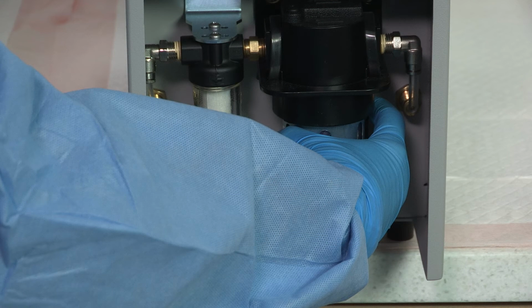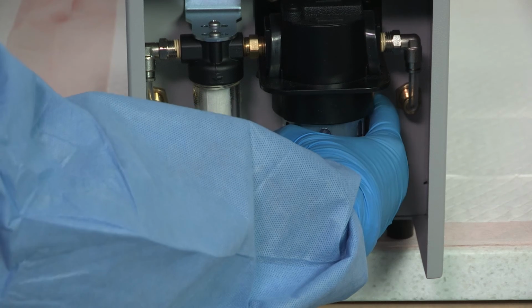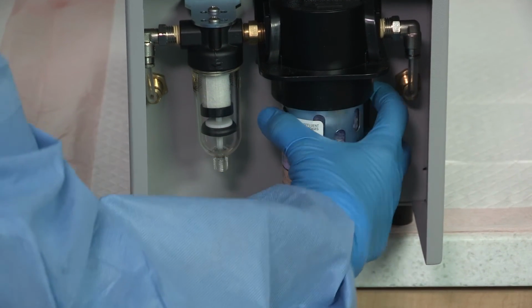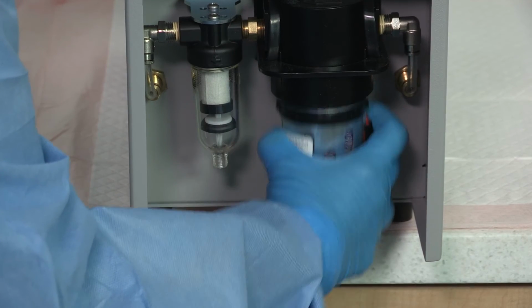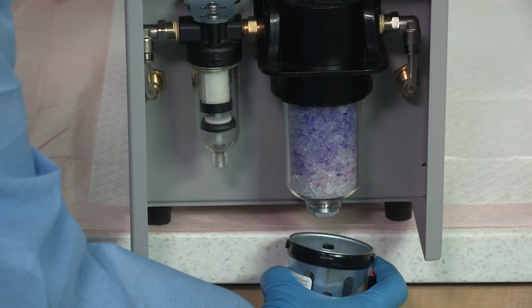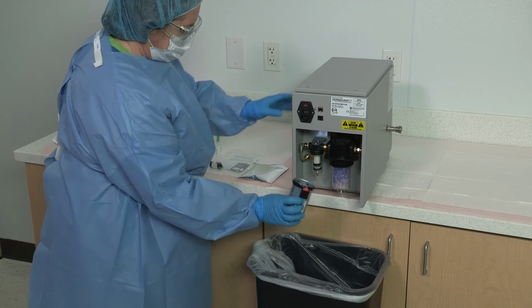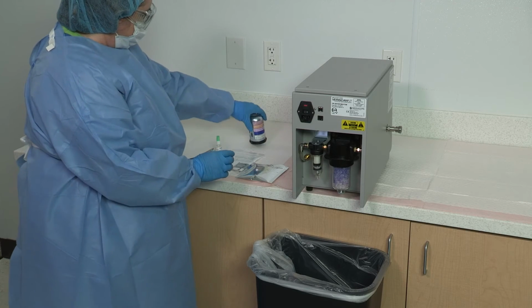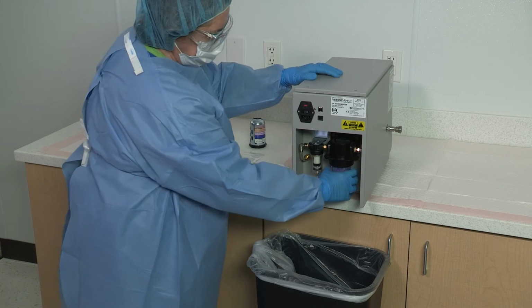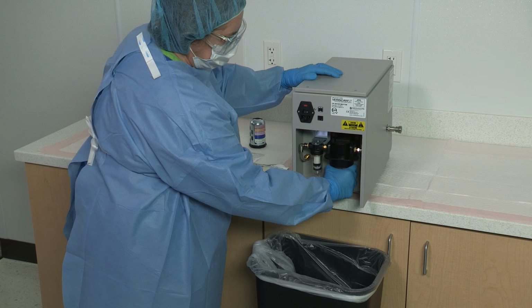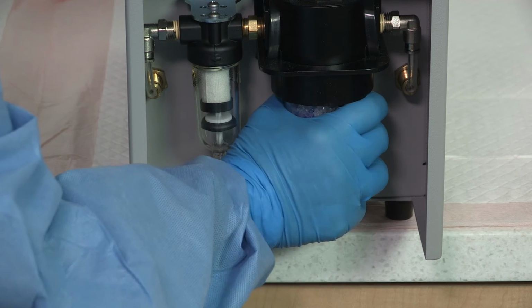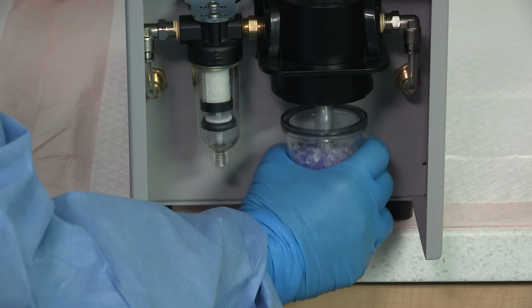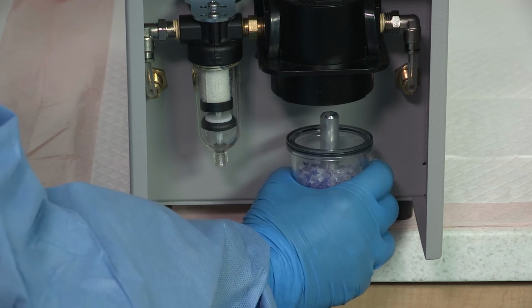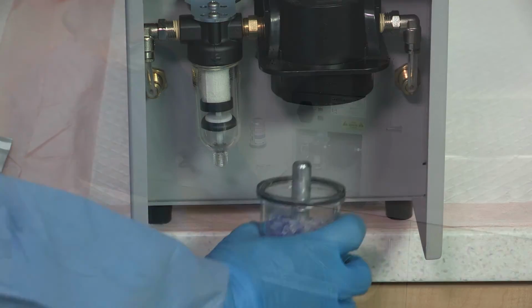The release button may be located in the back. Gently pull down on the metal bulb housing and rotate to the left until it releases down and away from the machine's bulb housing structure. Gently lower the bulb housing away from the machine. Remove the glass drying crystal bulb from the bulb housing structure by placing one hand on top of the unit, grasping the glass bulb with the other hand and carefully pull downward in a twisting motion until the bulb can be removed from the housing structure.